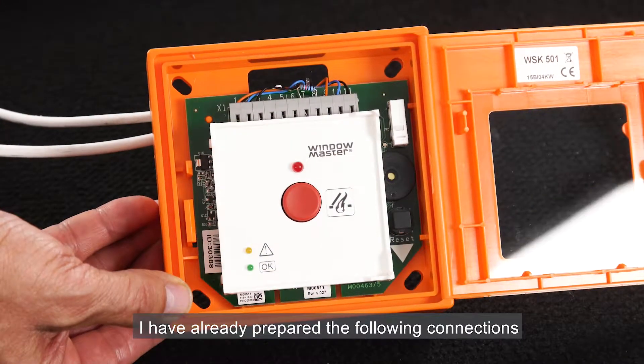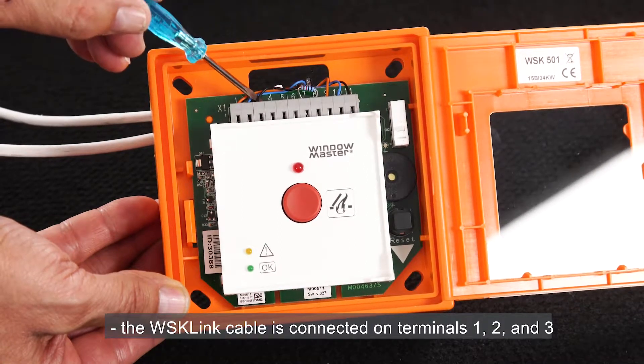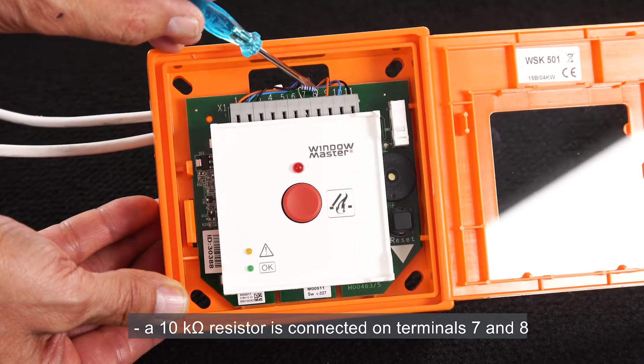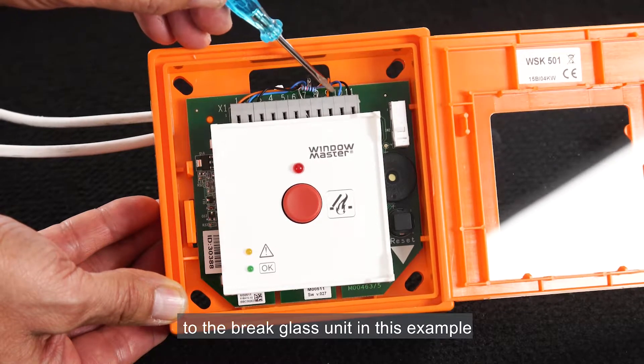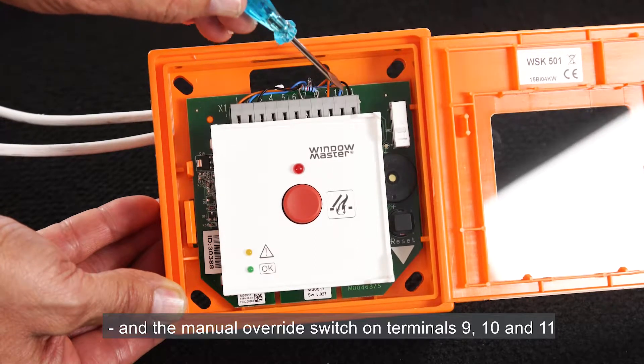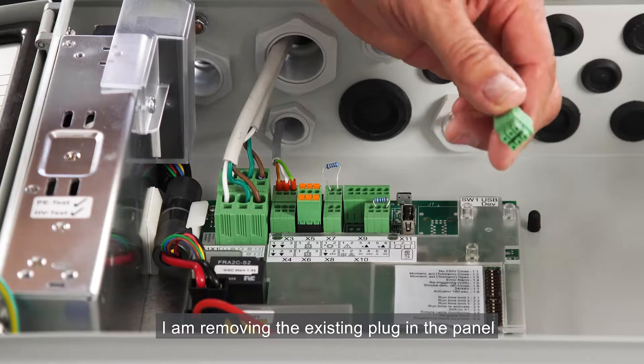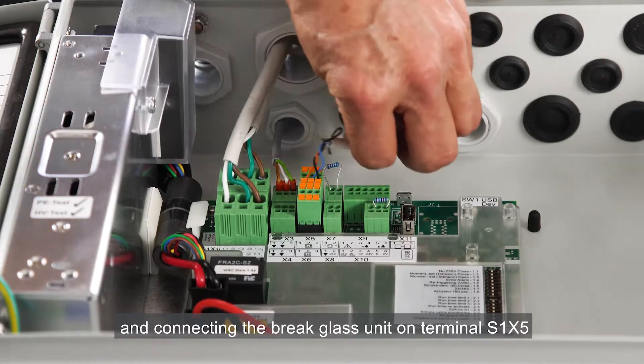I have already prepared the following connections on the break glass unit terminals. The WSK link cable is connected on terminals 1, 2, and 3. A 10 kOhm resistor is connected on terminals 7 and 8, because I'm not going to connect any smoke detector to the break glass unit in this example. And the manual override switch on terminals 9, 10, and 11. In order to connect the break glass unit to the panel, I have added a plug on the cable. I'm removing the existing plug in the panel and connecting the break glass unit on terminal S1X5.